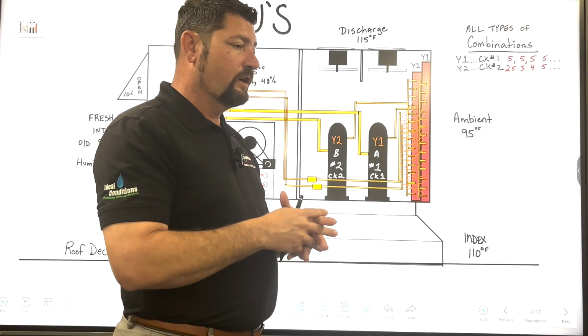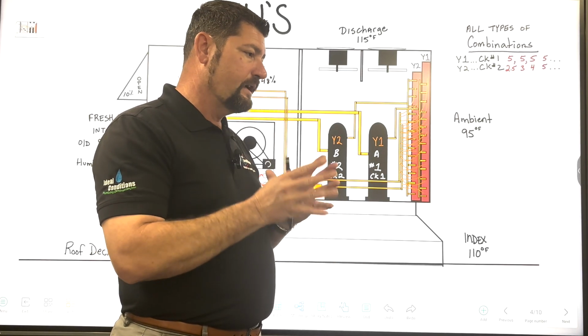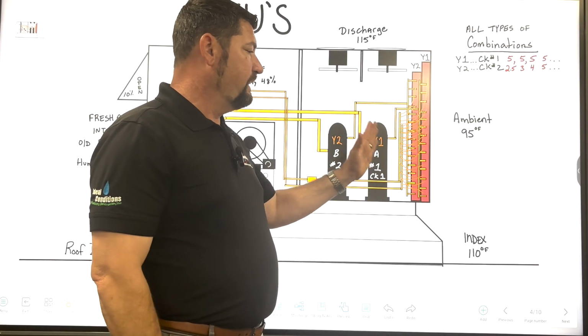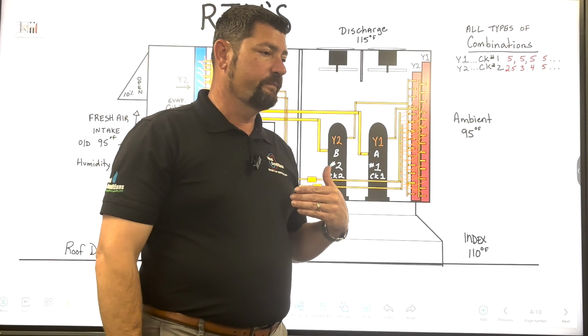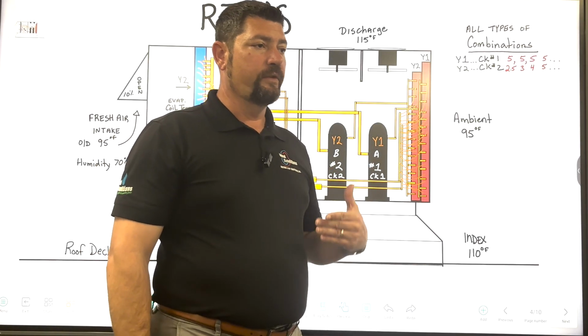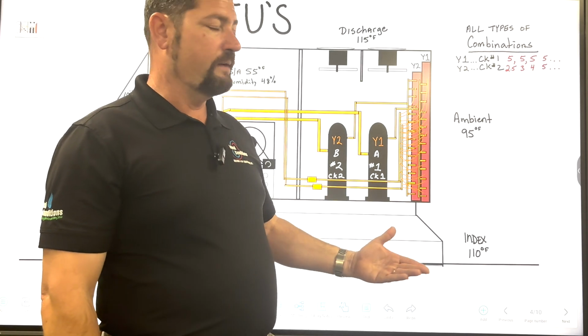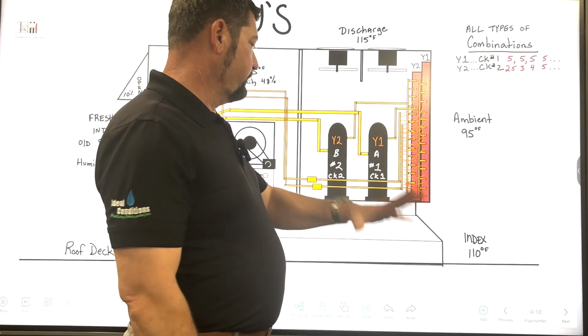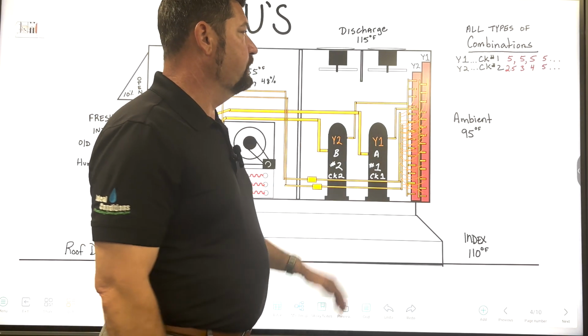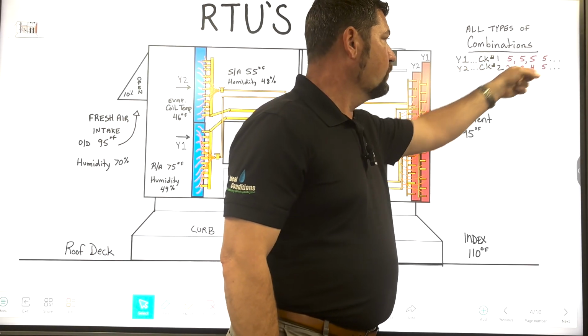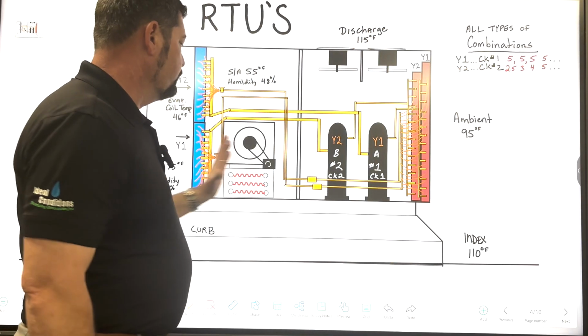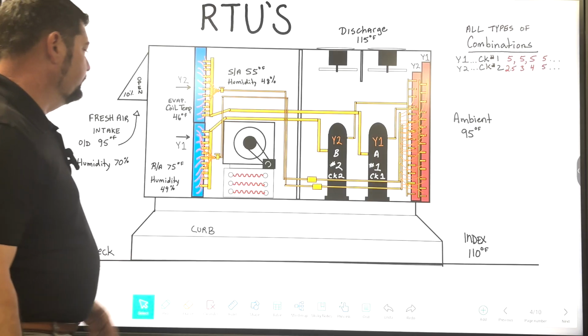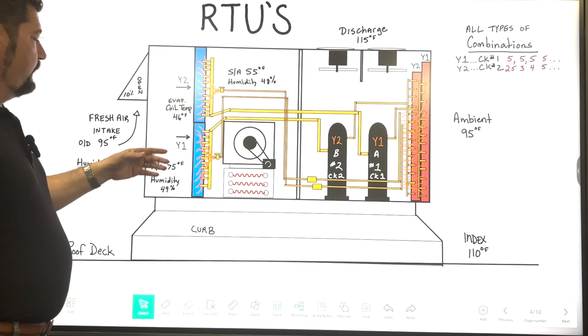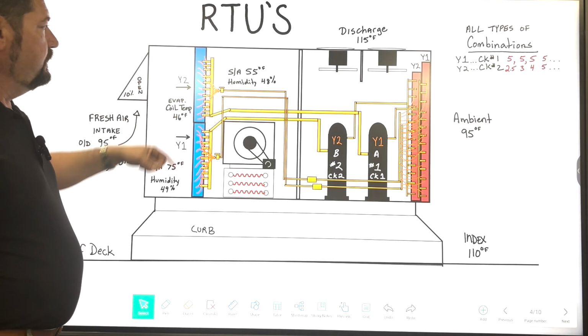But if that's the case, undo all that and make sure your thermostat is able to stage based off the demand. So if we start slipping away, with more than a 2-degree demand from set point, then the thermostat should naturally call for Y2, and then you'll naturally kick in more BTUs, being able to transfer more heat out of that building. So I've got Y1 down here, Y2 here.